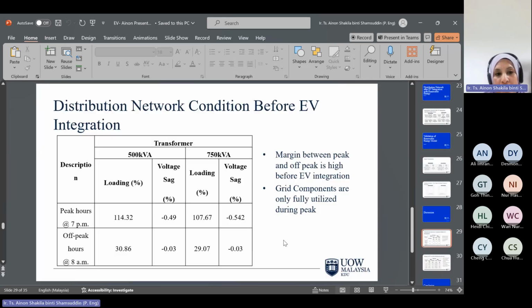So from all these results that we get, we make a conclusion of the discussion in this table. This table shows the data for both transformers before the integration of EV. The result shows that the system for both transformers is heavily loaded during peak hours and underutilized during off-peak hours. So this is not efficient, because most of the equipment in the distribution network is not fully utilized during the off-peak hours and only operates for a short period of time during the peak hours.